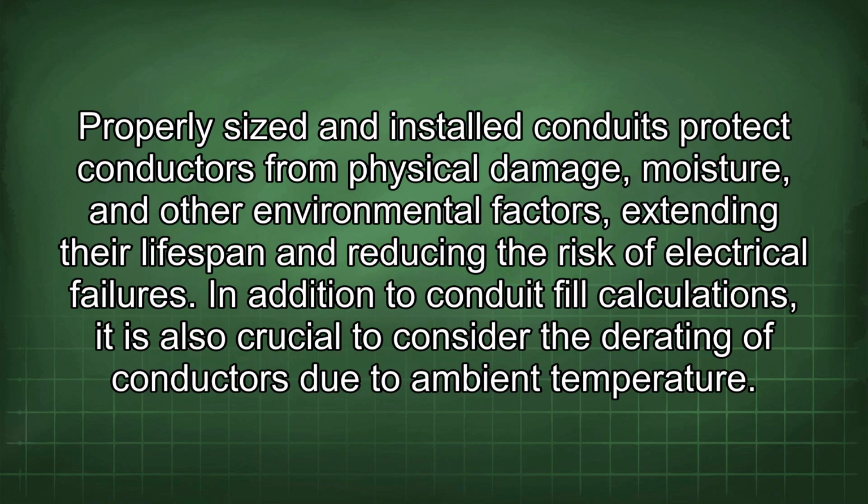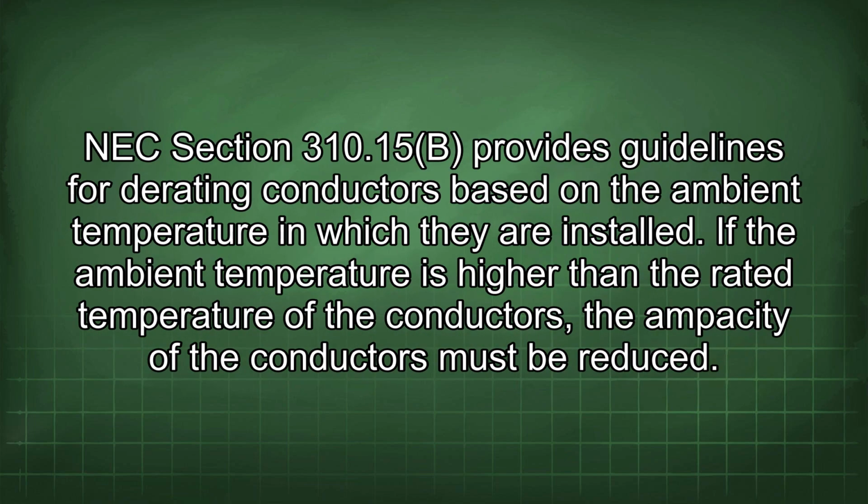Properly sized and installed conduits protect conductors from physical damage, moisture, and other environmental factors, extending their lifespan and reducing the risk of electrical failures. In addition to conduit fill calculations, it is also crucial to consider the derating of conductors due to ambient temperature. NEC Section 310.15(B) provides guidelines for derating conductors based on the ambient temperature in which they are installed.